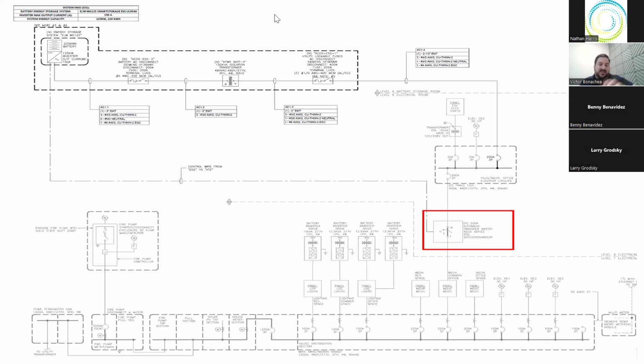It's kind of reverse. Usually you think about the sources on top and the loads on the bottom, like we talked about. In this case, it's a little bit backwards, but bear with me. On the bottom left corner, you'll see some transformers, and that's the utility feed coming into the facility that feeds all those boards at the bottom along the right with some of the loads on the facility. But then we see in the middle, there's a branch that's feeding up to that transfer switch within the red box. Feeding up through that transfer switch in the red box, you go a little bit higher up, to what's actually listed as the normal side of the ATS. It's actually feeding the utility in from the load side up to the normal side.